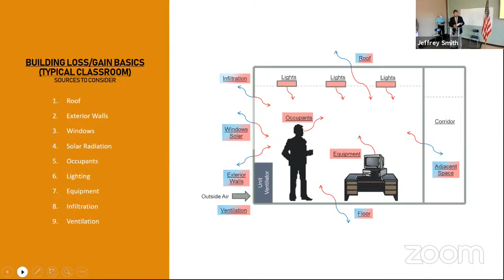Now we start to break it down into how we look at heating and cooling loads and what the biggest impacts are. I mentioned ventilation. If you look at the photo there, ventilation accounts for more than 57% of your heating load. So that is a big item that we can address in several different ways, and we definitely want to address. Then you have windows, infiltration, roof—all of those factors to take into account as we design, size, and select the systems.